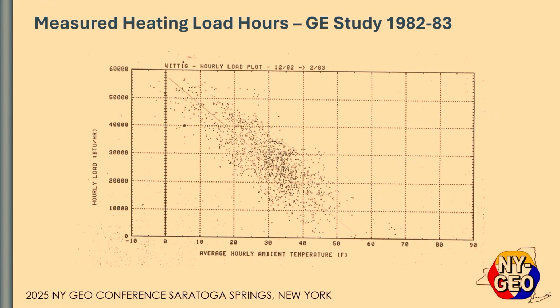But in reality, way back, GE did this study back in 1982. They actually measured the heat loss of a home and put a dot for every hour. So there should be, feel free to count on your own, 8,760 hours on this plot here. And when they plot the heat loss of the home relative to the outdoor temperature on the x-axis at the bottom, it will actually give you that load line, so to speak.